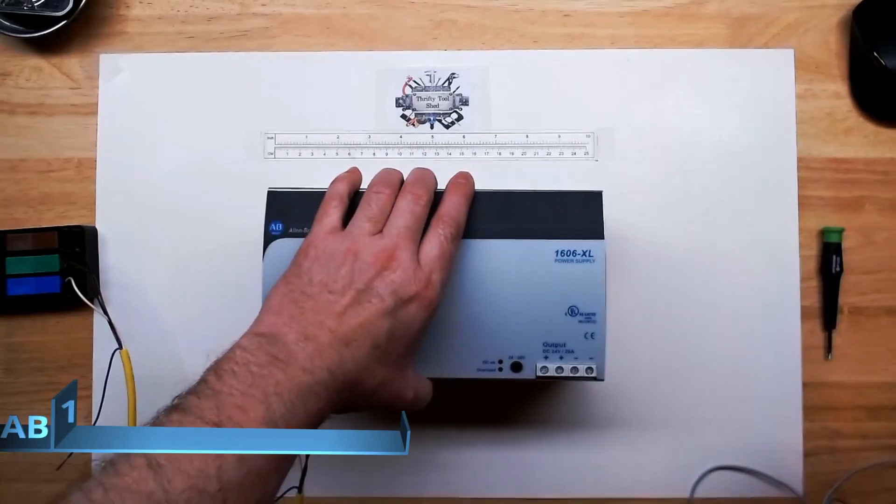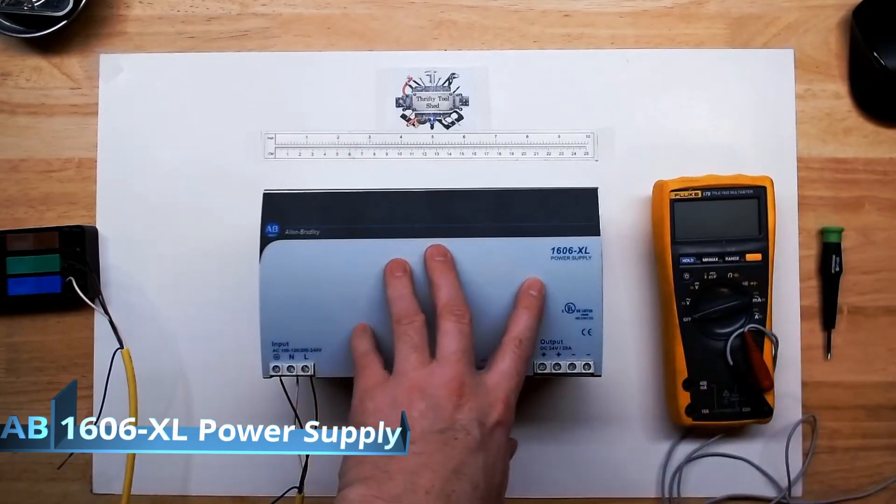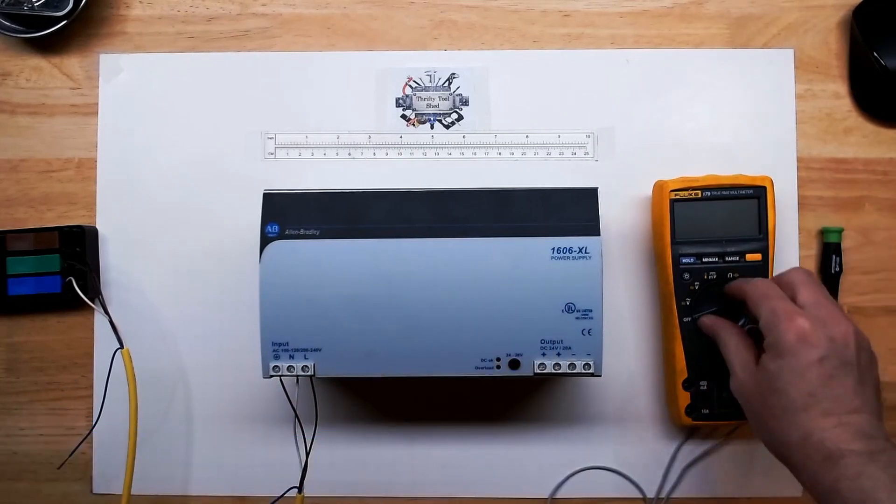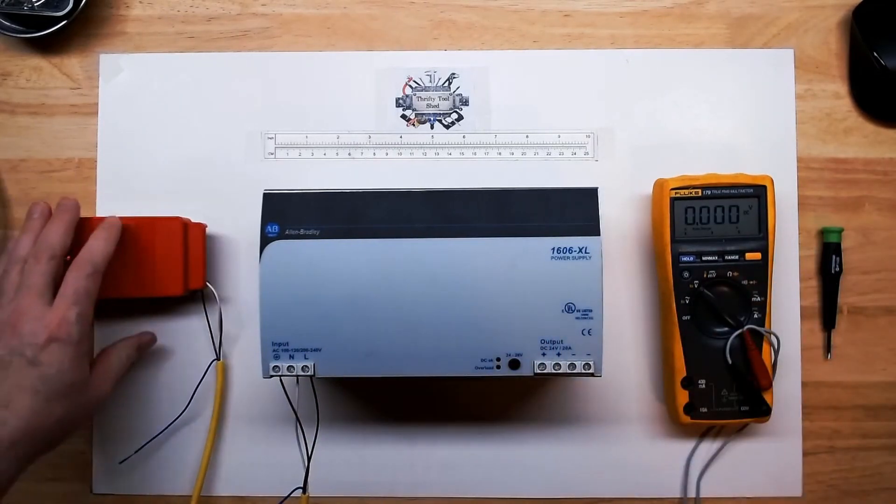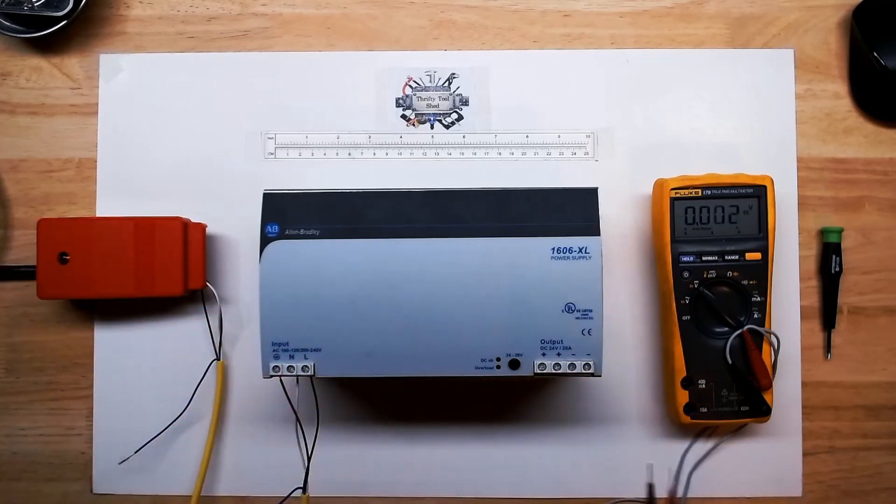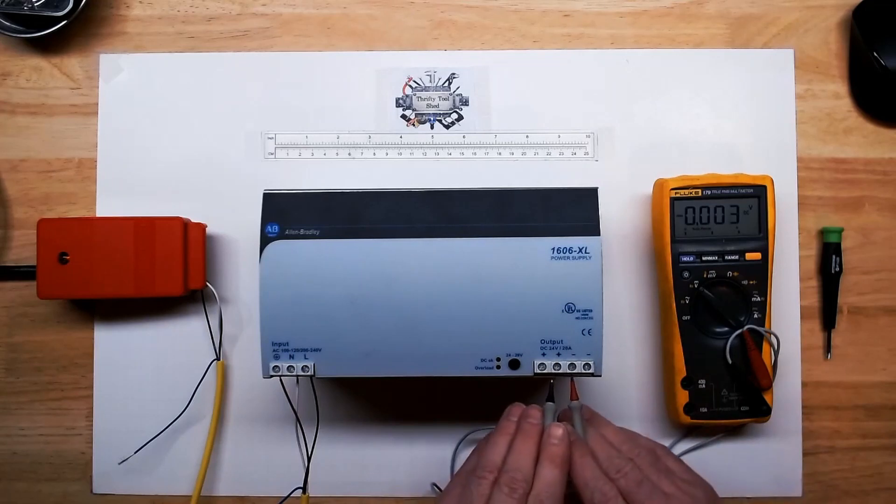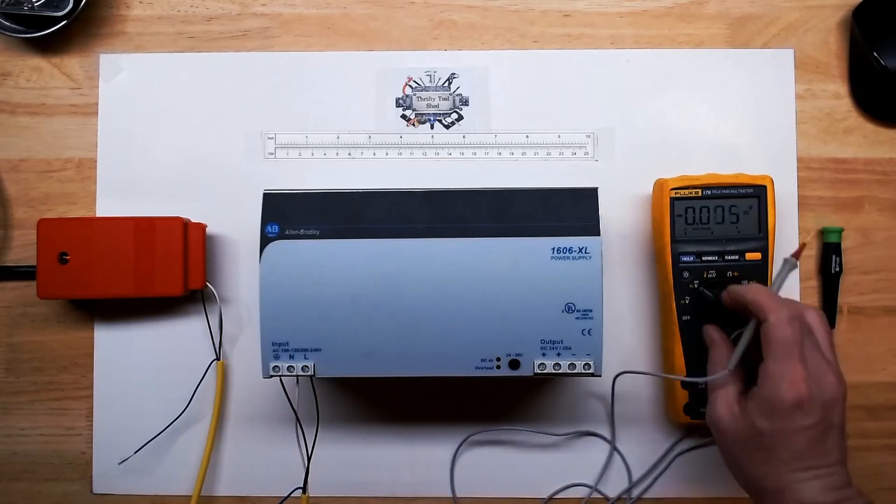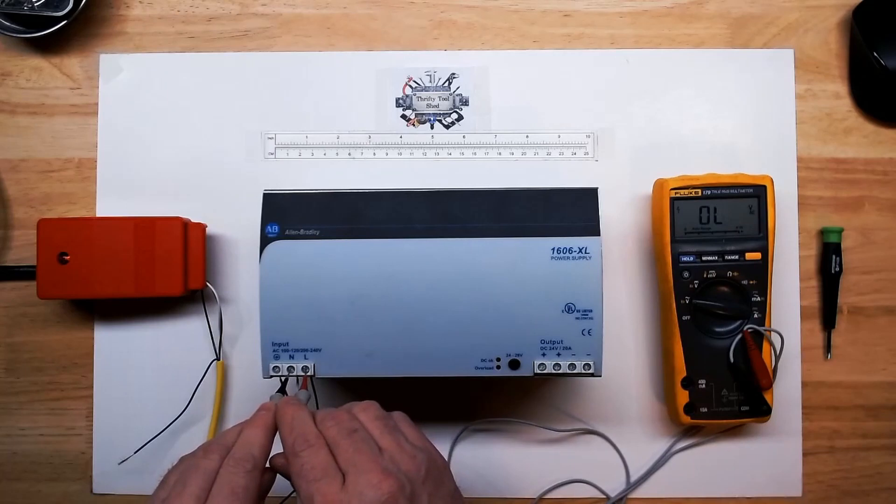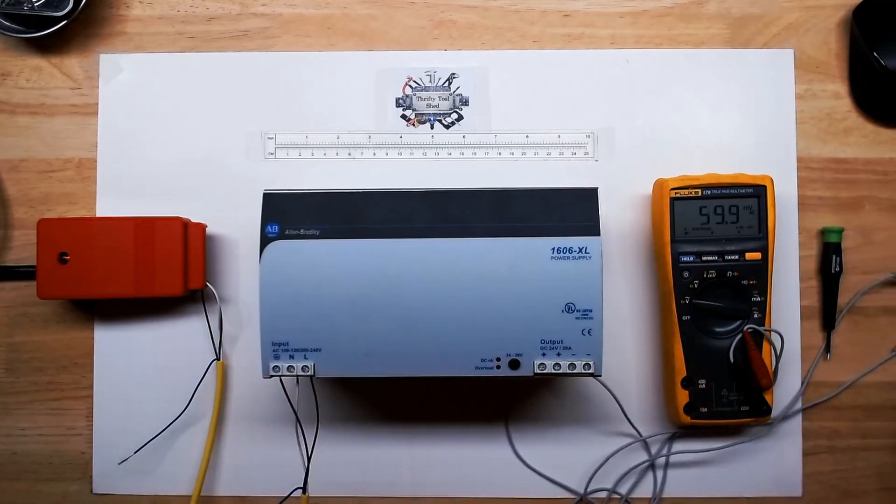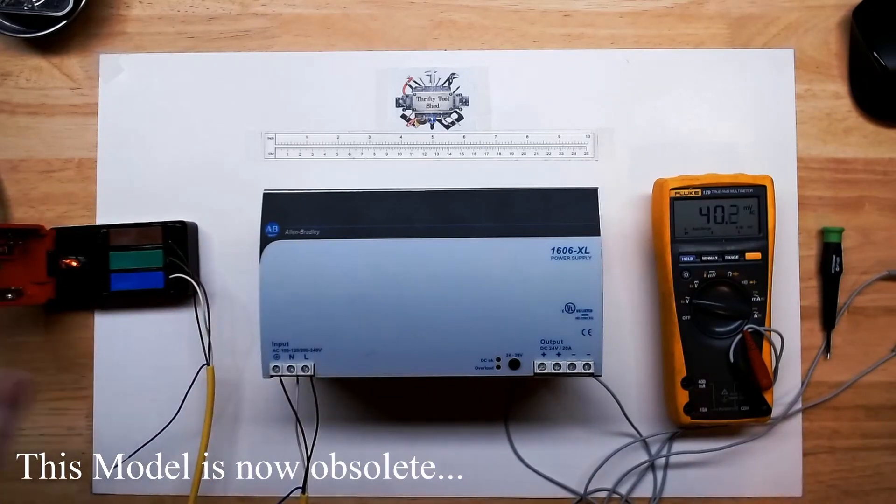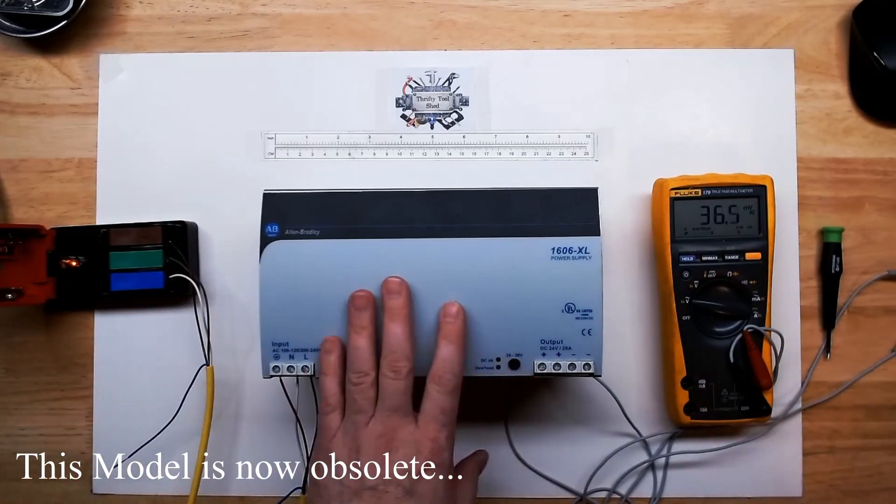Today I thought we'd take a look at this bad Allen Bradley industrial power supply. We'll bring over our quick test relay. We don't have any DC voltage on the bus there, just to verify. Here we do have 120 volts going in, so I'm gonna let these caps discharge and we'll take the cover off. Take a look inside with a T10 Torx bit.